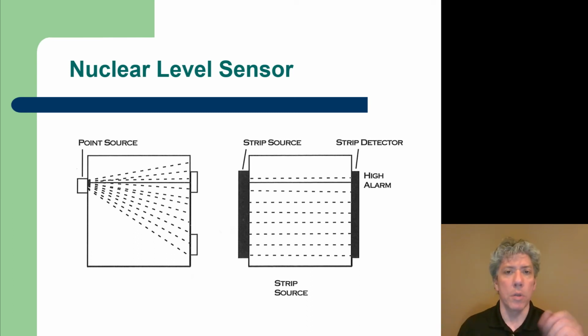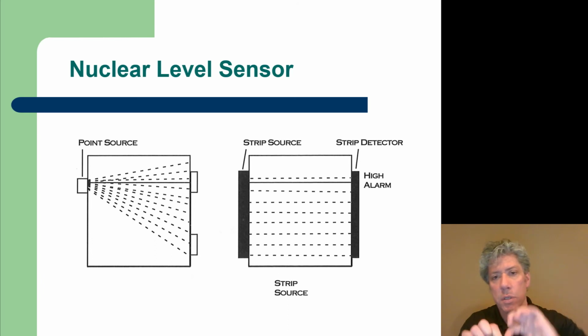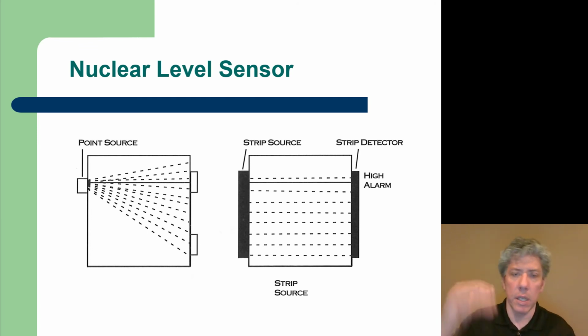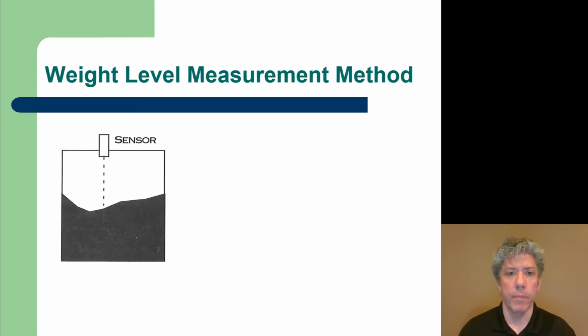Now, there are also strip sources of radiation, which is kind of like taking a flashlight beam and just spreading it out, so it comes from a whole line of points. And then a strip detector. Now, this is used for measuring varying levels in the tank. And of course, the more light that's sensed, the lower the liquid level must be, and therefore the lower the level in the tank.